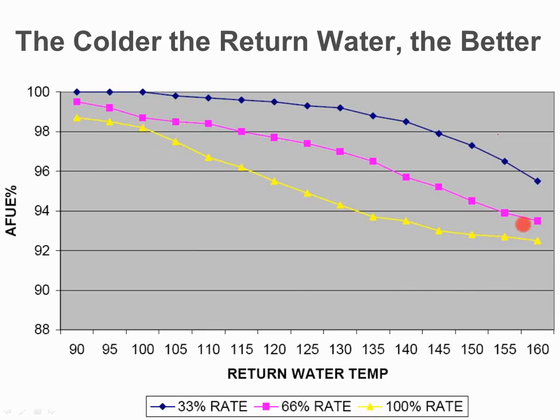So one way to save energy is to turn the water temperature down on the boiler. The other way is to lower the firing rate of the boiler. If I have a heat exchanger that's X big, and I lower the flame size, and I still have that big heat exchanger, it's going to take me less energy to heat that surface area. So if I lower the firing rate, in this case yellow is 100%, magenta or pink or whatever that is is 2/3 firing rate, and blue is 1/3, right? So even at peak water temperature, if I tell it to run at a lower firing rate, I can go from 93 to 95%. I can pick up 2% of energy savings just by keeping the flame low with a modulating type burner.